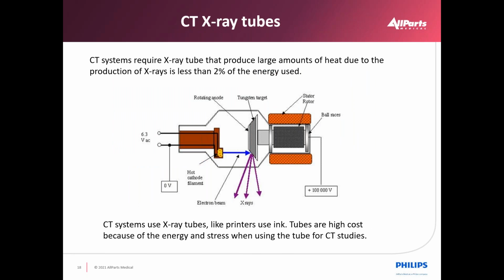So X-ray tubes. We typically see X-ray tubes fall in the category of about 2% efficient. So that means 98% of the time we're producing heat. So one of the design changes early in X-ray tubes was to have a rotating target so that the energy of that heat would be dissipated across the surface of the target. So the area of interest that we're concerned about is right where the blue beam hits the target and produces the purple X-rays in this event here.